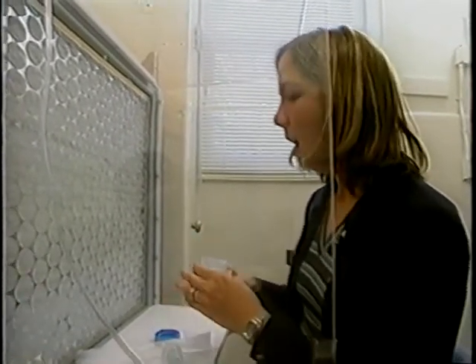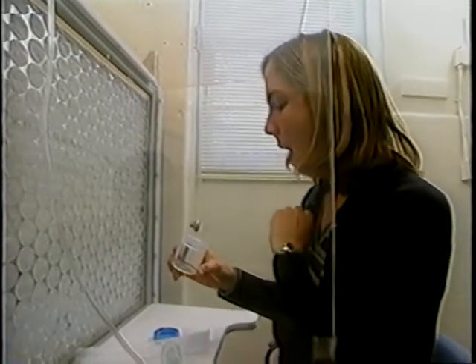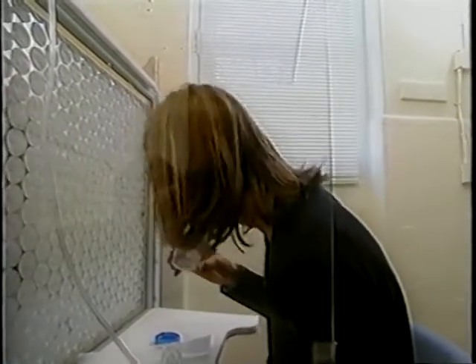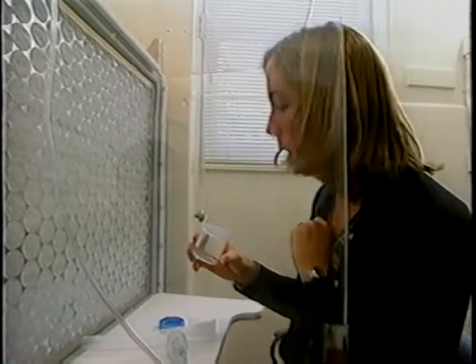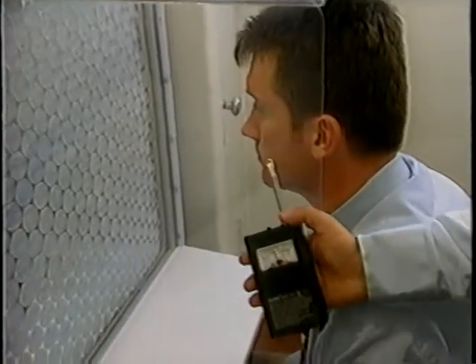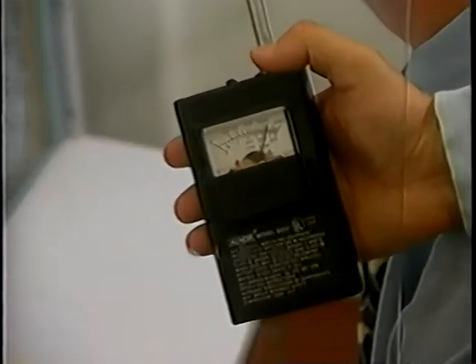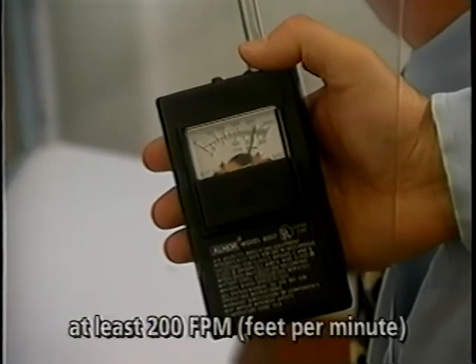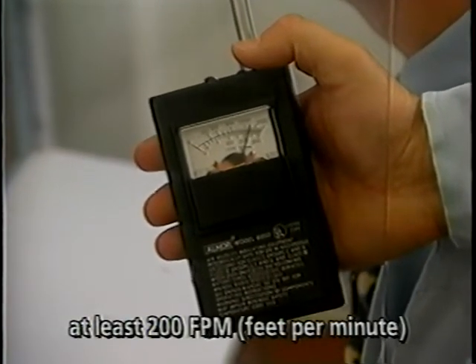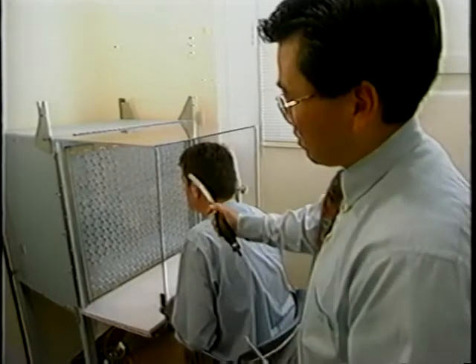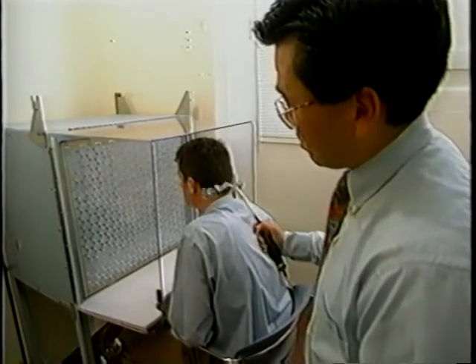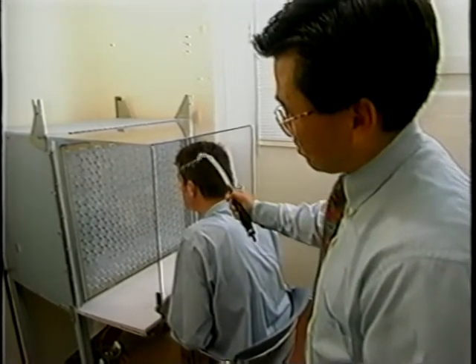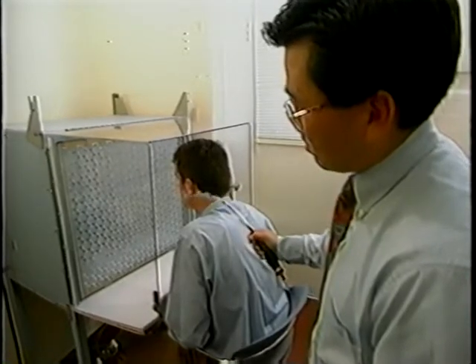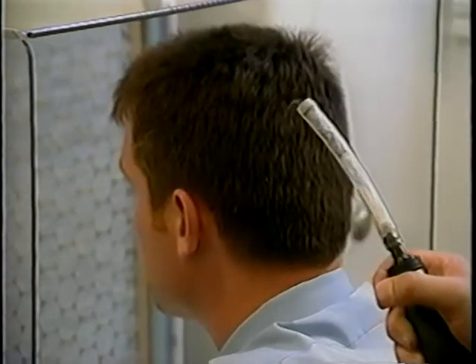The advantage of these devices is that they capture infectious particles so that they are not released into general room air. You should also check using a velometer that the air velocity is at least 200 feet per minute at the side of the patient's head. The hood should be placed away from other air currents, such as those created by open doors or windows. This can be verified by smoke testing.